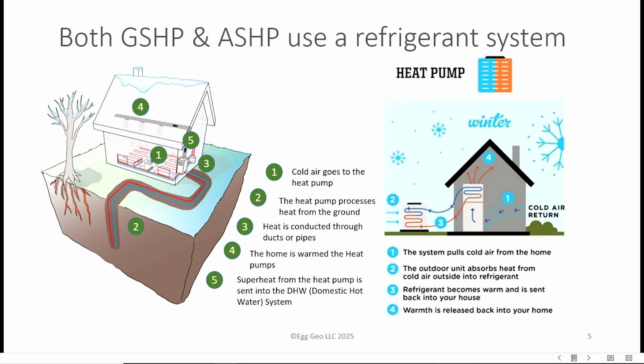Now, what happens, no matter how good of an air source heat pump you have, if it gets cold enough outside, the efficiency goes down to what we call a 1-to-1 ratio. And that means a 1 coefficient of performance. And a 1 coefficient of performance means that if you put 1 kilowatt of energy into a device, you'll get 1 kilowatt of heat out. Now, that's what an electric space heater does. And that's okay as long as the grid can handle it and your electric bill can handle it. But normally, these will run at about a 3 COP. If it's above freezing outside, they'll give you 3 kilowatts of energy for 1 kilowatt of energy consumption, because the 2 kilowatts come from pulling it from outside of the house into this refrigerant stream and then dumping it in the house.